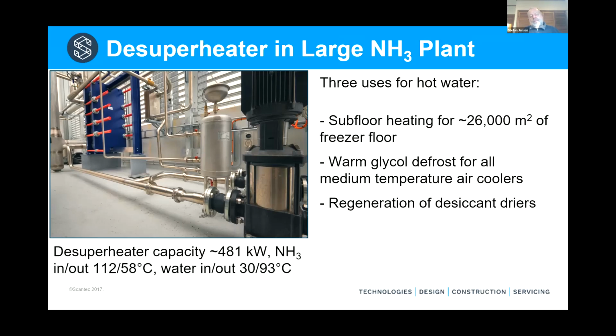Secondly, we use the warm water that comes out from the desuperheater. It's in the order of the usual part, generally about 80 degrees, 90 degrees or 93 degrees, as you see there on the picture, when we're running 35 degrees condensing temperature. We try not to do that, of course, because it uses too much energy. So we let the condensing temperature float, and then the available temperature from the desuperheater floats down with it.